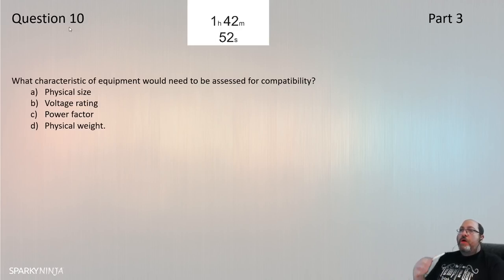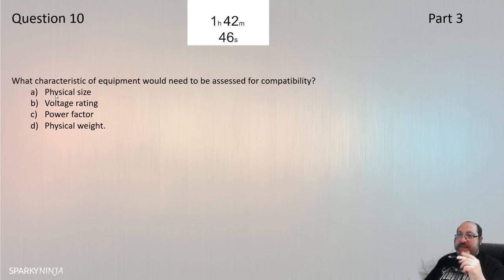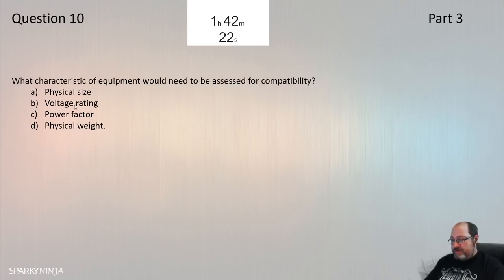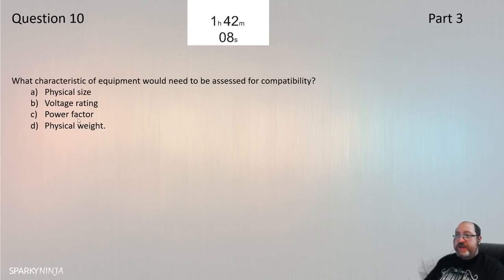Question 10: What characteristic of equipment would need to be assessed for compatibility? The clue 'characteristic' points to Chapter 33 — compatibility. Scanning through 331.1: transient over-voltages, under-voltage, unbalanced loads, rapidly fluctuating loads, starting currents, harmonic currents, earth leakage current, high frequency oscillations, and at the bottom — power factor. Question 10 is C — power factor, from 331.1, 12th item in the list.